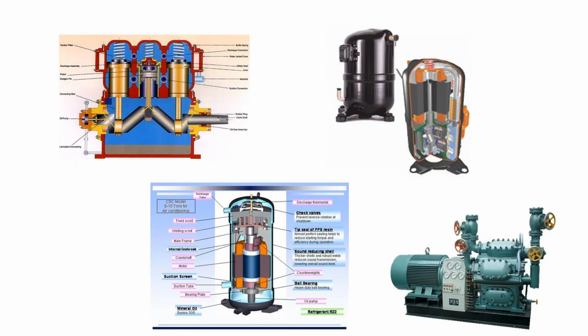So the examples here, that's a cutaway. Those pistons compress the refrigerant in a cylinder, and there are valves at the top that either let the refrigerant in or let it go out. You see these in hermetic. Those are the ones, those black ones over on the right, or semi-hermetic, the one in the bottom right corner.